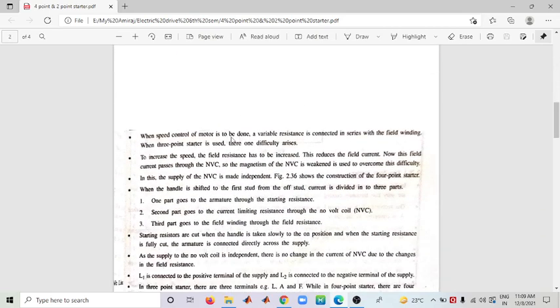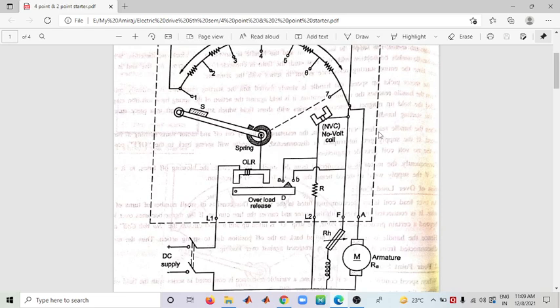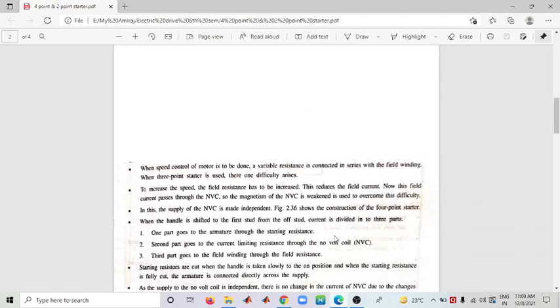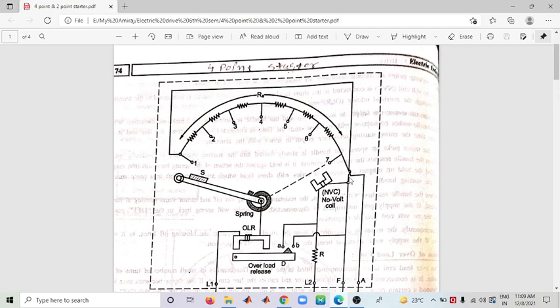When speed control of the motor is done, a variable resistance is connected in series with the field winding. When the Three Point Starter is used, there is a difficulty: when speed is increased, field resistance increases, which reduces field current. Now this reduced field current passes through the NVC (No Volt Coil), and the magnetism is reduced — this is the problem that needs to be overcome.